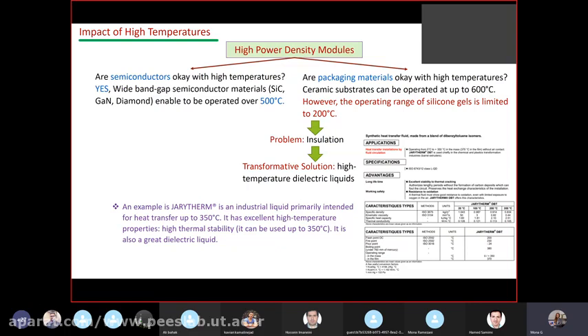What can we do other than managing these high temperatures using cooling methods? The transformative idea here is using high temperature dielectric liquids. For example, there is an industrial liquid primarily intended for heat transfer at 350 degrees Celsius. It has high thermal stability, low toxicity, and is also a great dielectric liquid. That's one of the transformative ideas—you can replace the silicone gel to get the answer.